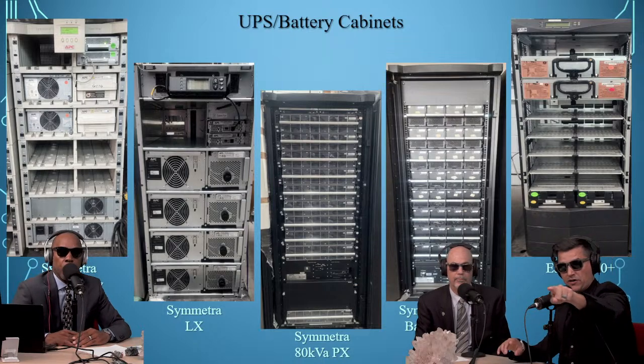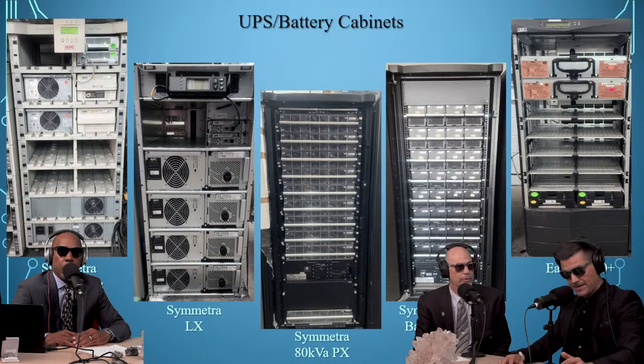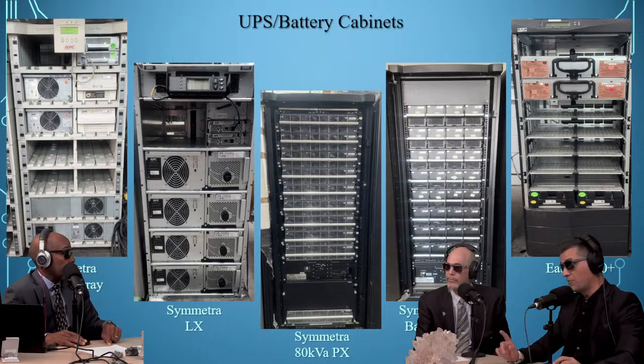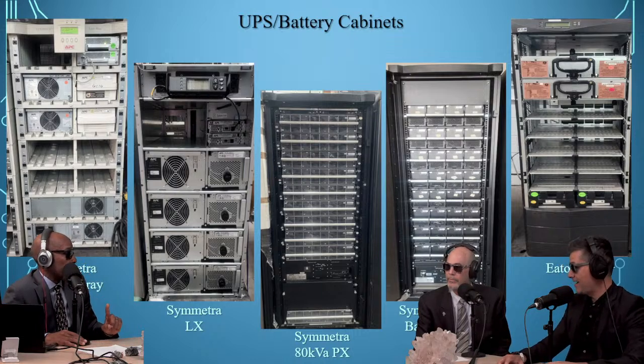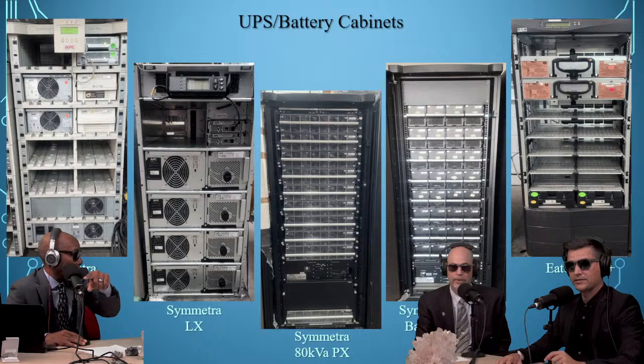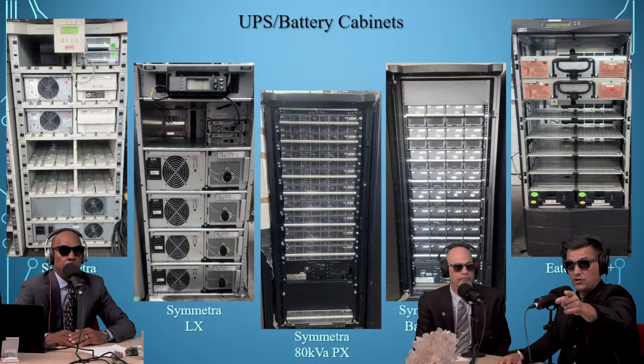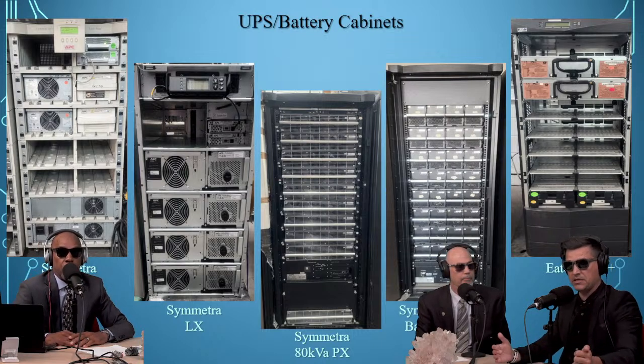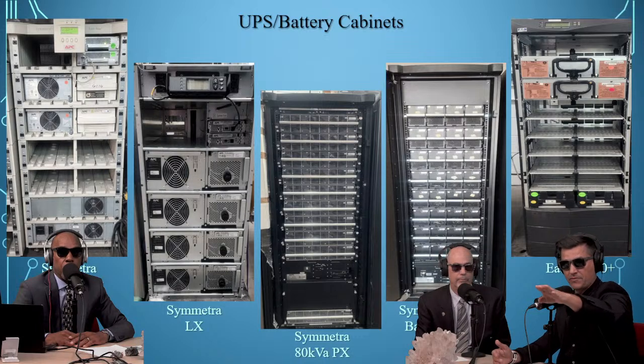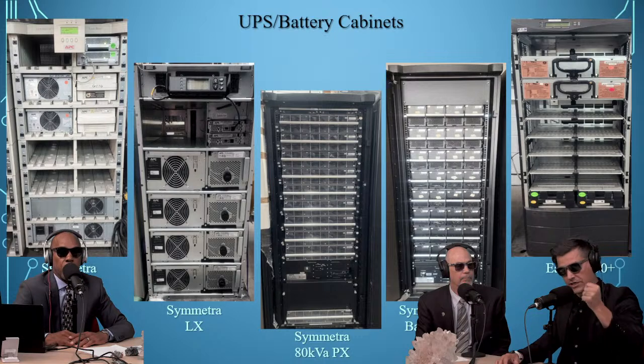That's a string of 4 on a shelf, each one a battery module. So there's 32 there — 32 battery modules, 8 strings, because a string is considered 4. If you take one out, APC and industry standards say if you take one out from that string, you want to replace all of them together, but you can just take one out at a time.